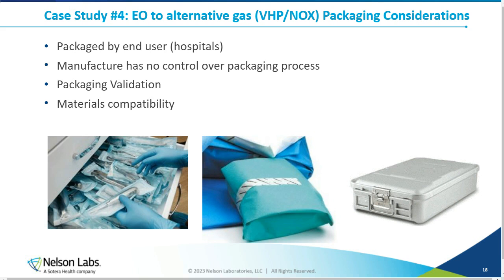You'll see types of packaging such as these pictures I have below. This is just a little medical-grade paper film pouch. It's not a heat seal pouch. It's an adhesive seal. And those are more problematic because you don't have any control over the closure of your packaging. Part of the packaging validation is really validating that you can close this sterile barrier and make sure that it's consistent every time. And you lose that when you have someone else, or many someone elses, package the product. Another type of common sterile barrier system that's used in a hospital is surgical wrap.